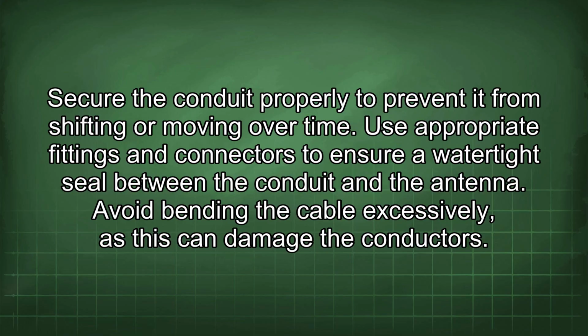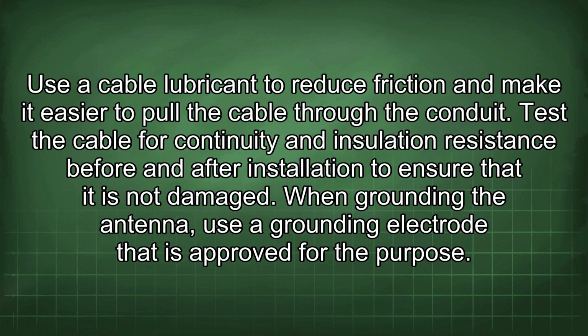Avoid bending the cable excessively, as this can damage the conductors. Use a cable lubricant to reduce friction and make it easier to pull the cable through the conduit. Test the cable for continuity and insulation resistance before and after installation to ensure that it is not damaged.